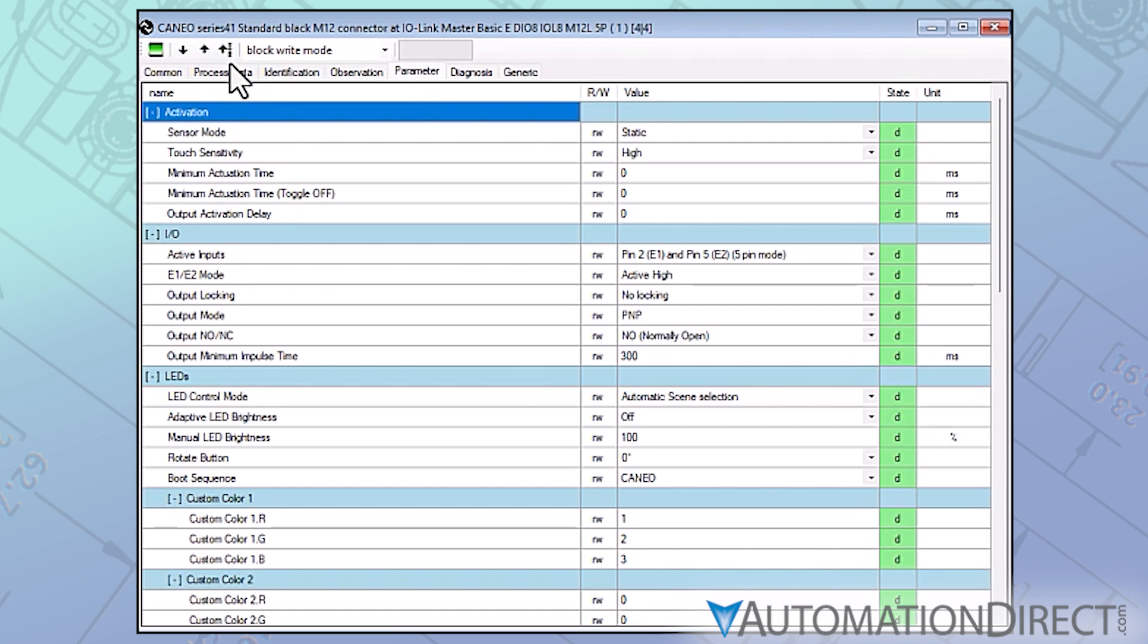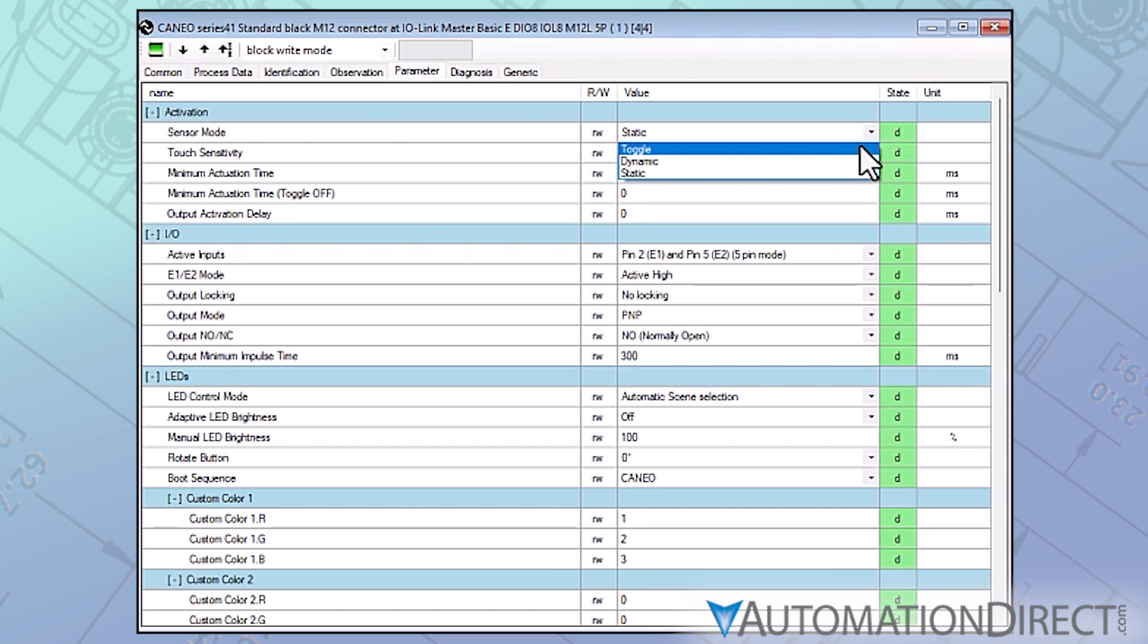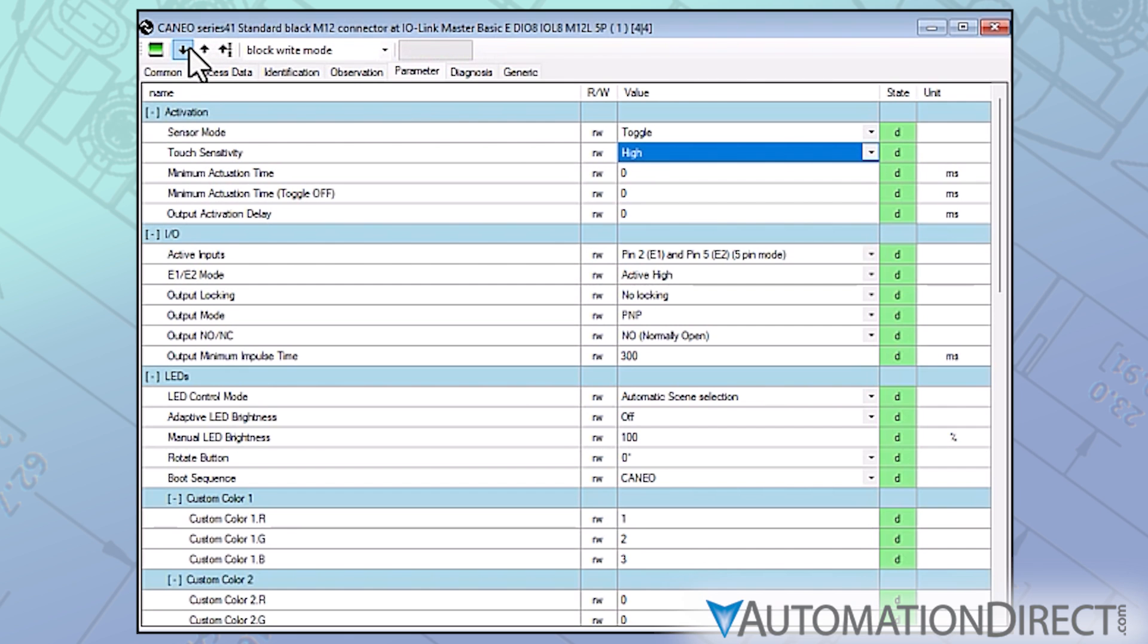Read-write variables marked as RW, such as those on the parameter tab here, can be downloaded to the device in a couple of different ways. In block-write mode, all changes made since the last download will be transferred at one time. Notice change parameters show a yellow C, indicating that they have not yet been written to the device. Once transferred, they turn green again.